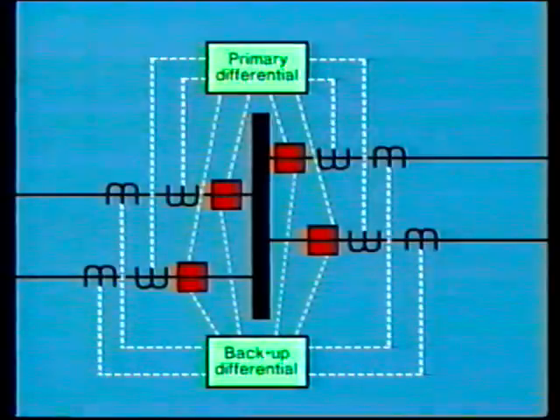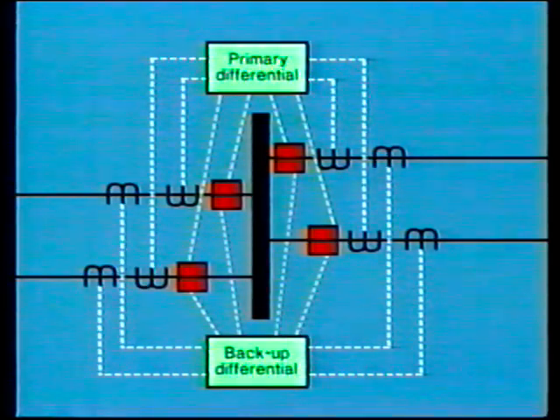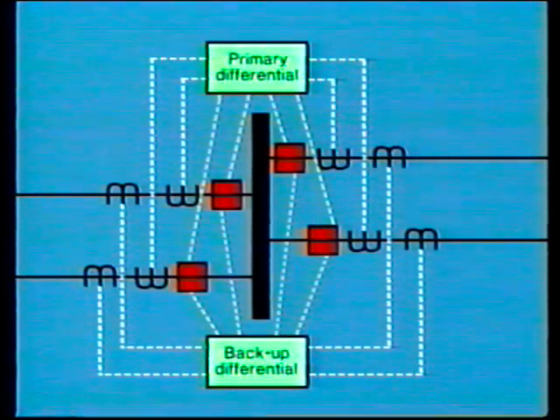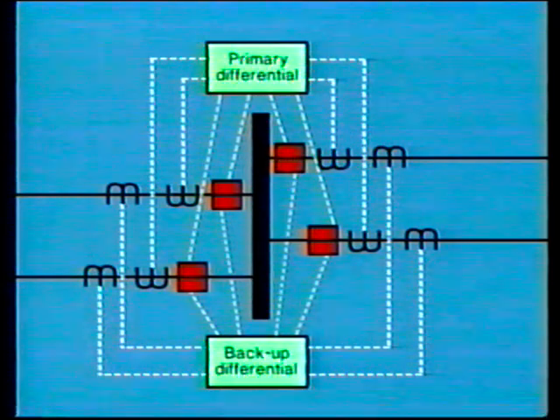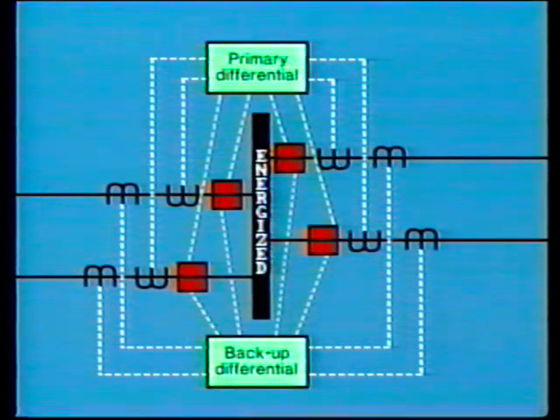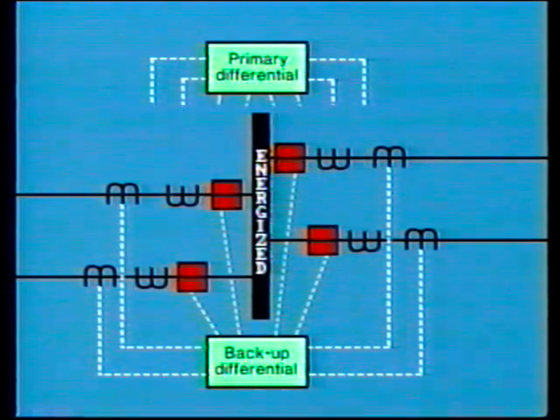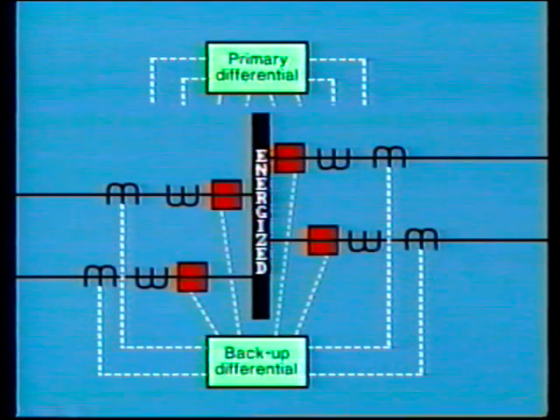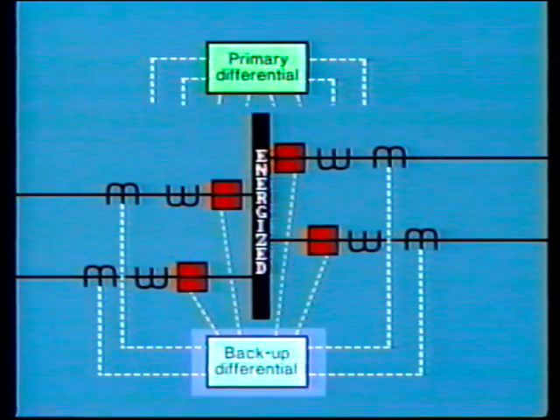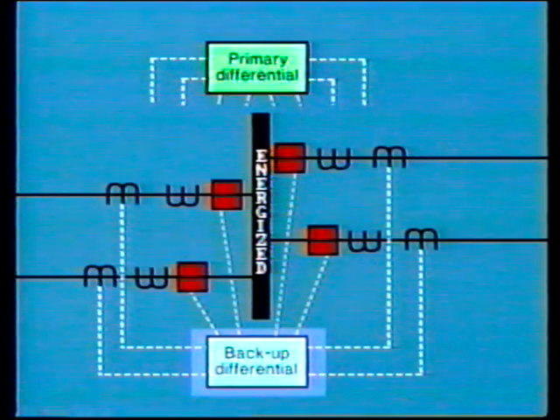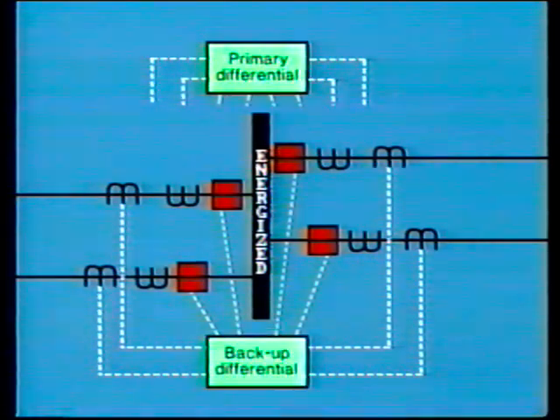In performing the tests, there are many other precautions that must be taken, but before we look at these, let's first view some case histories and learn about some recurring problems. In this case, two technicians were calibrating and testing the bus protection scheme. The test was carried out with the bus energized and the primary differential protection scheme isolated. The redundant backup differential protection scheme remained in service to protect the live bus.